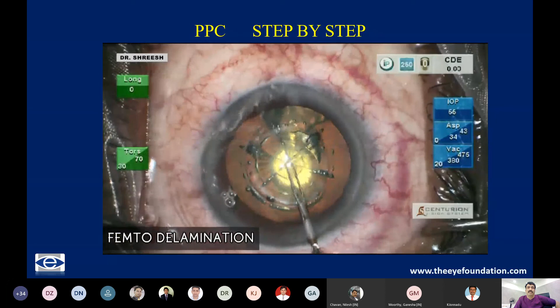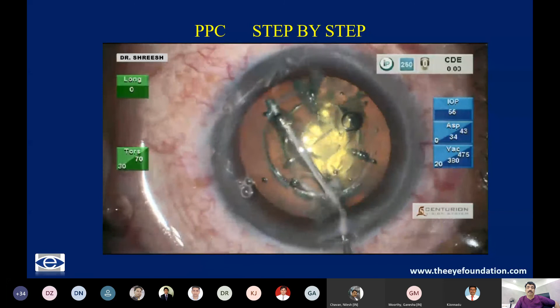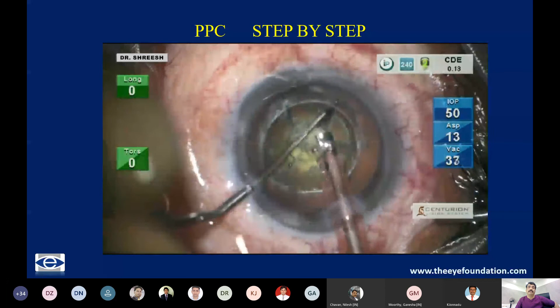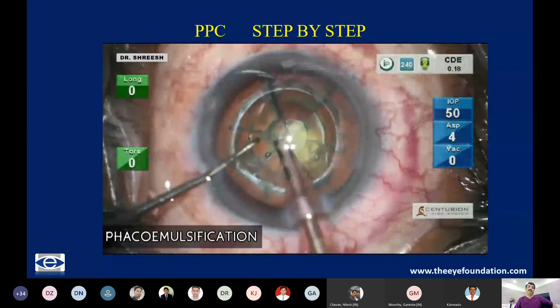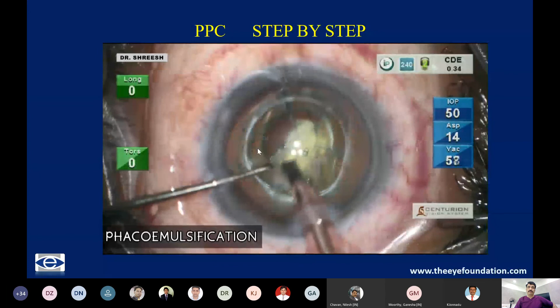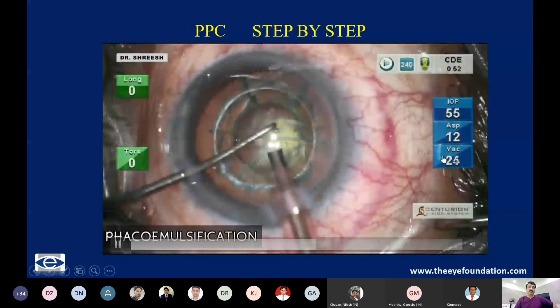Once this is done, you take him to the other theater, and it's not a hydrodelamination, you're just burping. There will be an air bubble, you just have to release this air bubble so that you have some space, and try to remove these cylinders with low energy. The IOP, if you see here, is low, 50 millimeters of mercury, and the low aspiration flow rate, and the vacuum is also low.